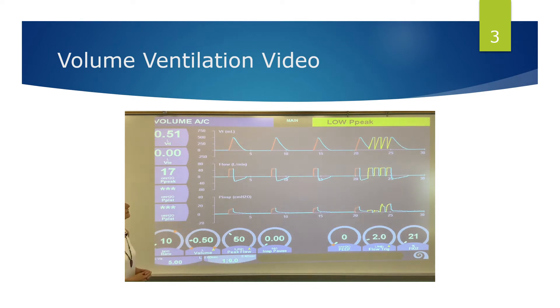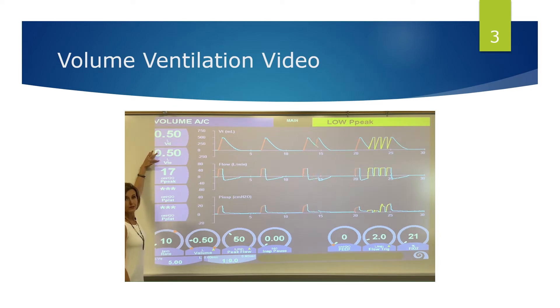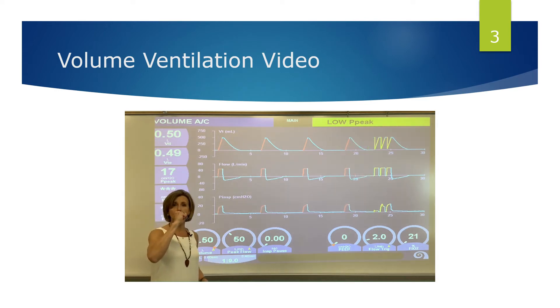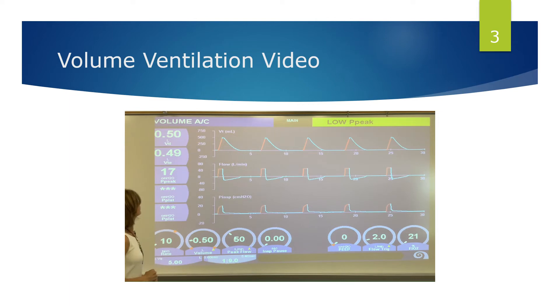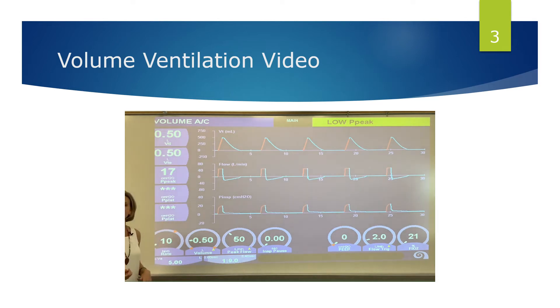With the bronchospasm simulated: we're still pushing 500 mL of tidal volume in, still getting pretty much 500 mL back out, but now it's taking a pressure of 17 to do it — because when the airway is smaller it takes more pressure to push that volume past a smaller opening. This is how volume modes of ventilation work: we set the tidal volume and it does not change, but what changes is the peak inspiratory pressure. Changes in compliance and airway resistance will fluctuate those peak pressures.